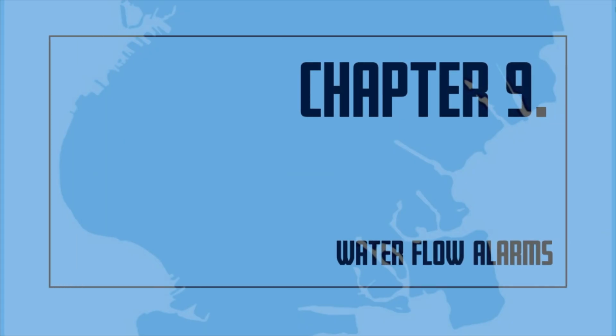Chapter 9. Water flow alarms and sprinkler system supervision. Sprinkler systems should have devices and equipment for signaling when water flows through risers or mains supplying the systems. The flow may be due to fire, leakage, or accidental rupture of the piping. It is important that prompt action is taken when water flow is signaled by these devices.